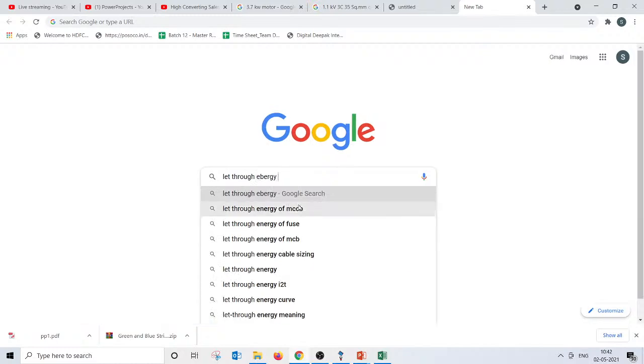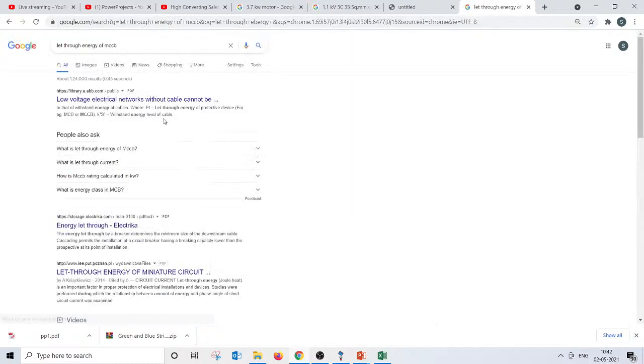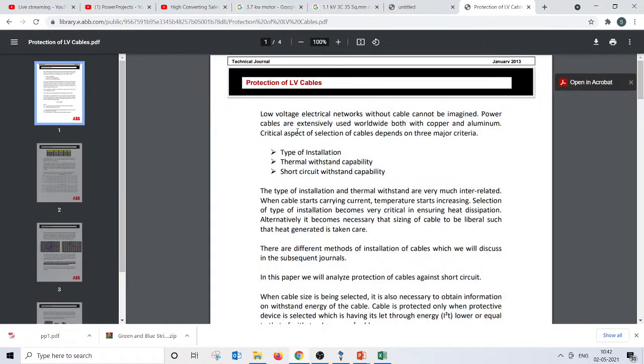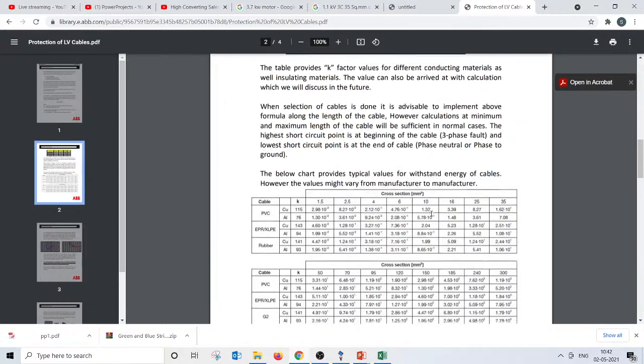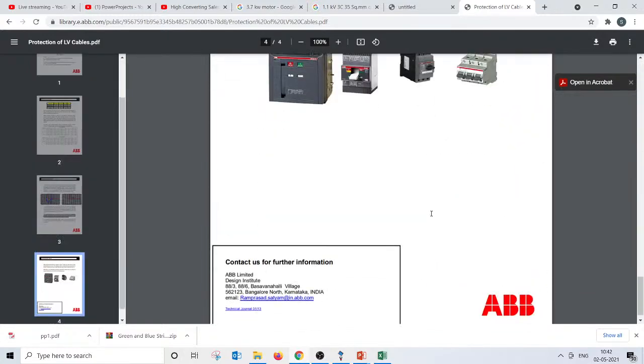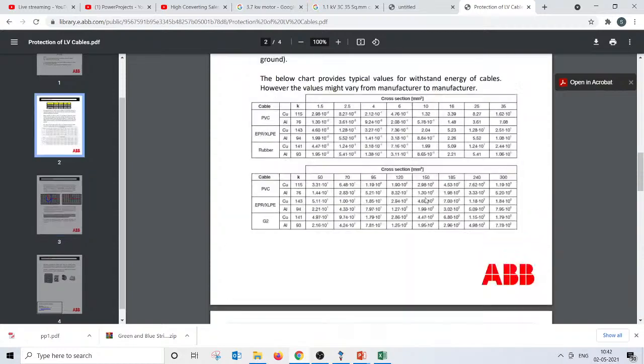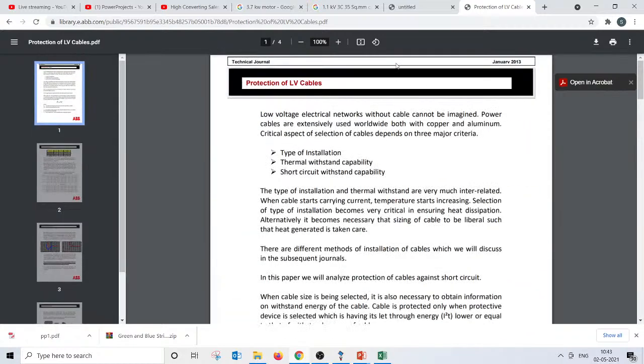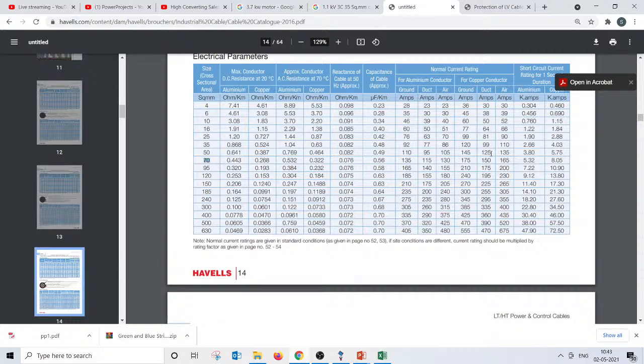Yeah, you can find out the let-through energy of an MCCB if it is a current limiting type. Probably, for example, ABB gives you the let-through energy of these circuit breakers, and you can probably find it in the catalogs. And for that let-through energy, you have to compare it with the cable short circuit withstand.